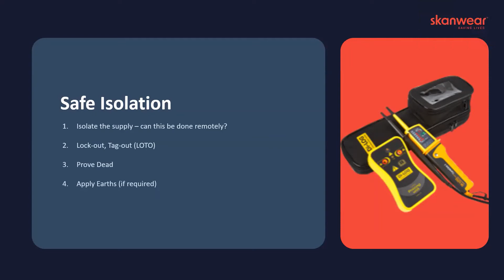It's not a myth. Okay, so safe isolation. So isolating supply, can this be done remotely? If you can run remotely, it removes the wearer or the person from the actual point of isolation, from the area where there's a risk of arc flash. It removes them out of the way of that situation, that zone. So if something does happen during the isolation period, the wearer or the person operating the equipment is right out of the scope of the arc flash should something go wrong.